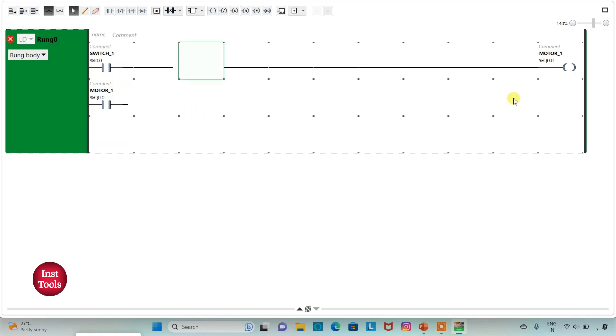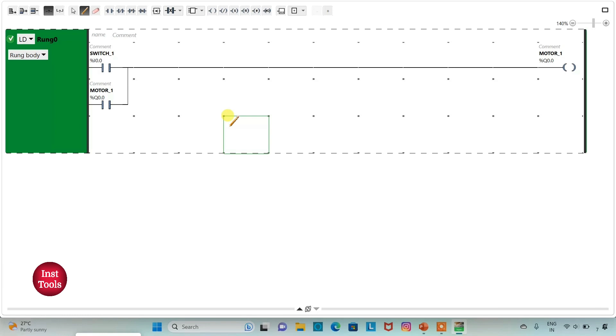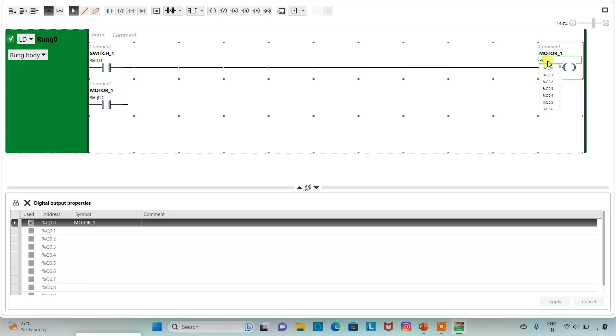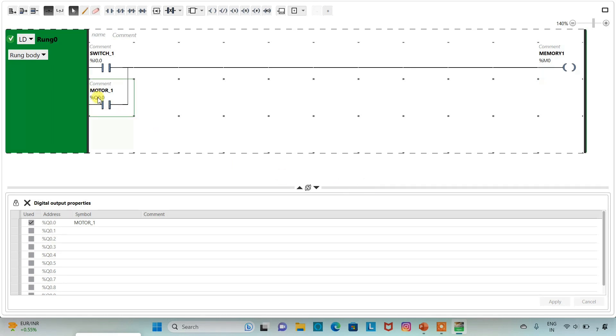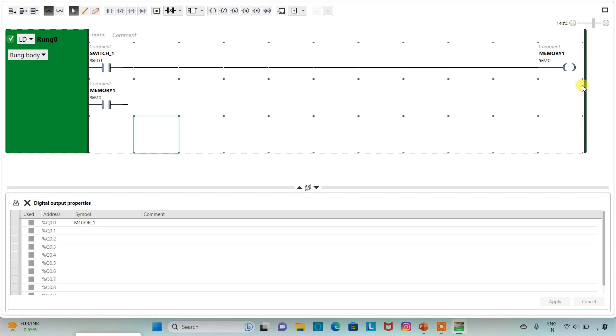So when SWITCH1 is on, MOTOR1 will be on, and when I turn off SWITCH1, MOTOR1 will still remain on due to the latch. Instead of drawing the same ladder for MOTOR2, we can use a memory bit — I will assign address M0 with symbol MEMORY to the coil, and update the latch contact address to M0 as well. So when SWITCH1 is on, MEMORY1 will be TRUE, and when SWITCH1 is turned off, MEMORY1 will still remain TRUE.